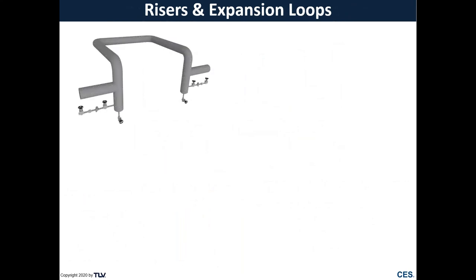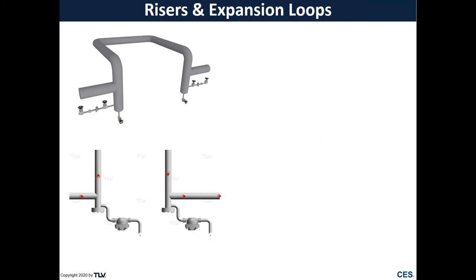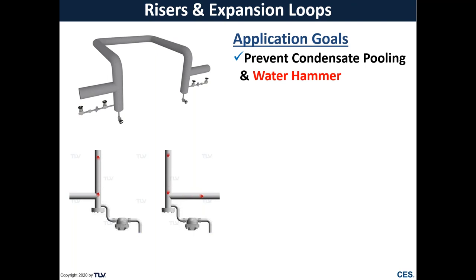Risers and expansion loops: we often see changes in elevation in steam systems, either going over roads or around objects, or just accounting for the thermal expansion of pipe. The application goals here are we want to avoid condensate pooling, which can lead to water hammer. Of course, condensate does not want to go uphill, so it will not naturally go up these risers. We need to drain it before and even after that riser.